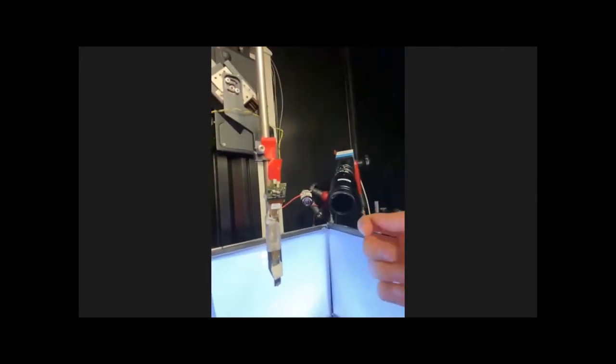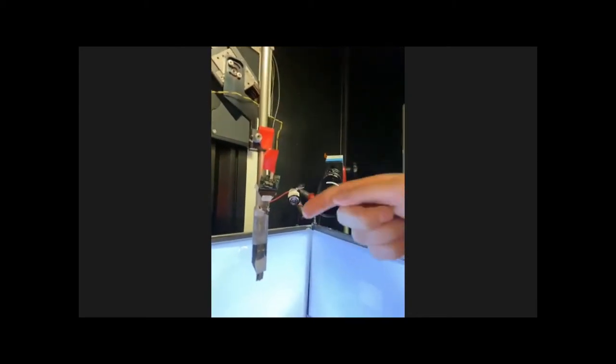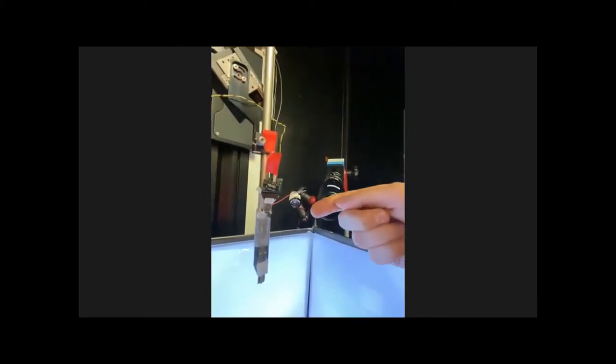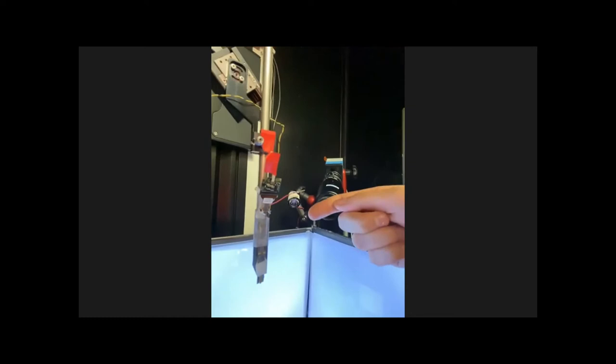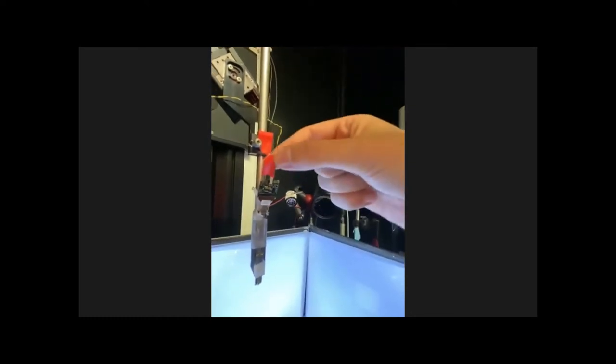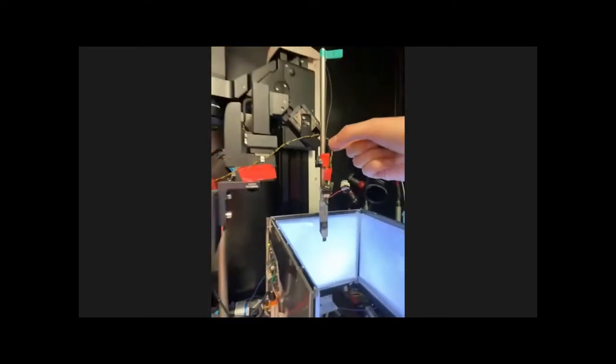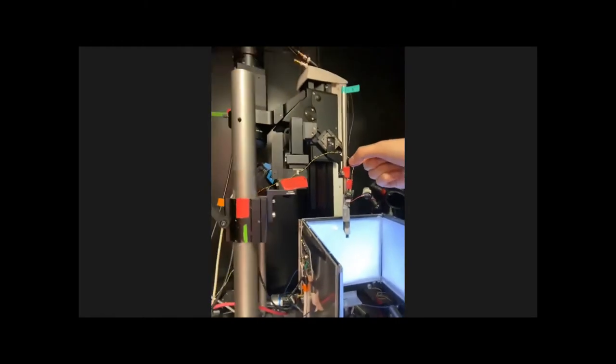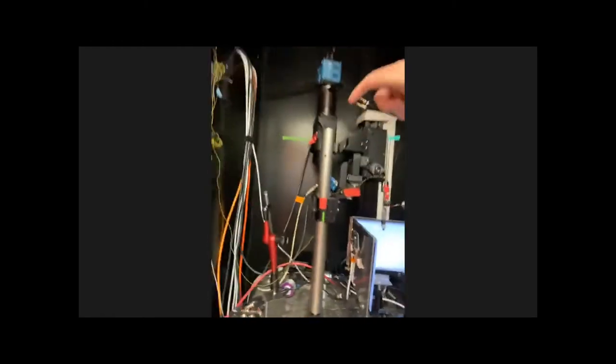A head stage, and as you can see, one of the really nice features of Neuropixels probe is that it has a really small footprint, so my finger for scale. You can really easily insert a lot of probes simultaneously, and I think the record is eight or nine, which is quite a lot. And then all of the signal is amplified, digitized, and filtered on base, and the signal comes out from one single cable, which is really nice.